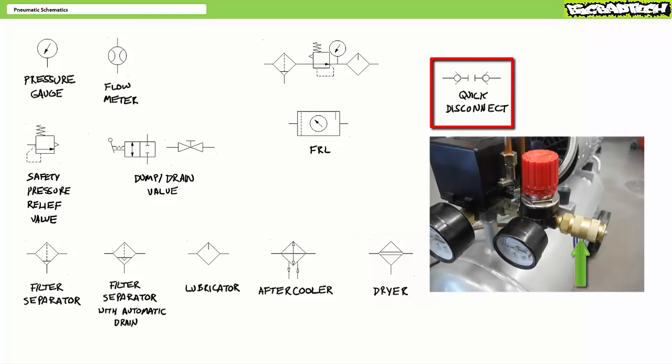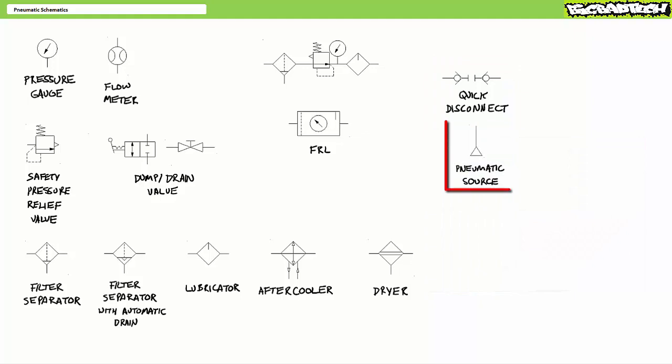Lastly, you might see a push to fit quick disconnect fitting illustrated at the output of the compressor circuit. When a matching fitting is inserted in the quick disconnect, it pushes the poppet off the seat and allows flow from the pneumatic source to the circuit. Since compressor circuits can get a little busy, one might find the entire compressor circuit, including the motor prime mover, compressor, receiver, regulator, and all the accessories simplified as a single empty arrowhead pointing into the system. Using a simplified symbol like this really cuts down on the busy work.